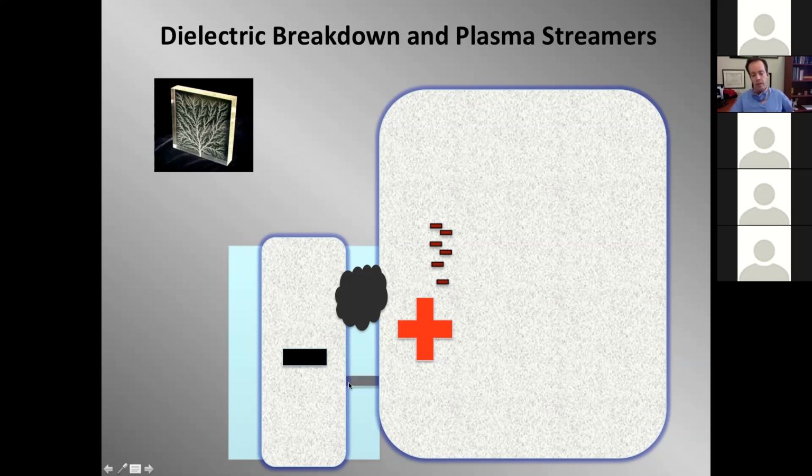Alternatively, you can have a through and through fracture, but just enough insulation capability of fibrin that it's just far enough that low voltage doesn't create the plasma arc. But then when you create that high voltage, you get what Chuck Swerdlow and Mark Kroll call plasma streamers, that blow the hole and create that arc, that low impedance arcing, which basically shunts all the current through your breach and none of the current to the heart.